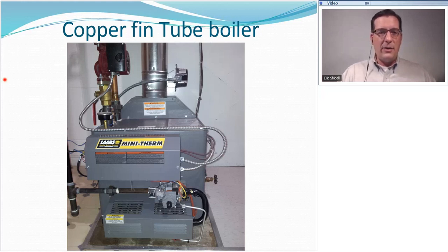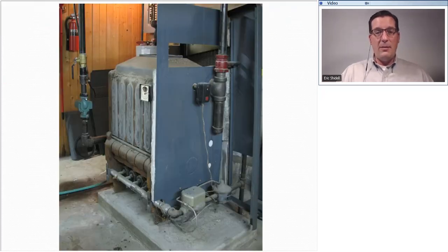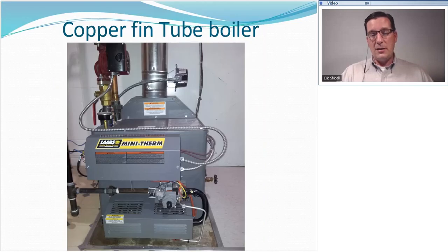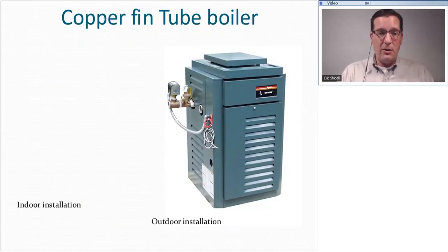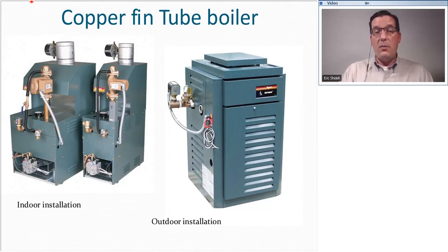This boiler that we're looking at right now is probably going to do the same heating job as this boiler here, which is much, much larger. So copper fin boilers pack a large punch into a small space. You can tell by their name that they are made out of copper, and I'll show you one of the heat exchangers. You can buy copper fin boilers for multiple applications.